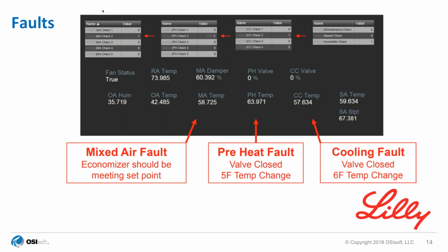So now I'm probably going to have 5 times increased energy consumption by using electric reheat at the terminal units for something that should have cost me no chilled water or hot water. It should have been met just through mixed air and damper percentage. I am now spending 5 times my energy cost because of these systems. And these systems crossed multiple air handlers. Next page.